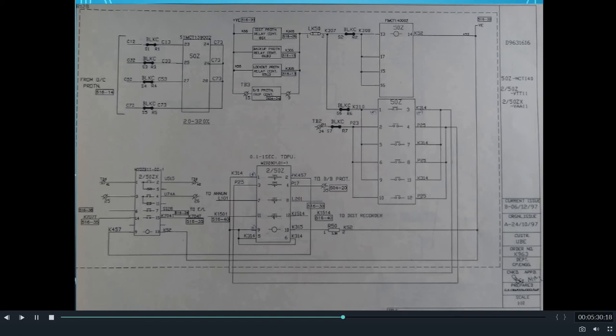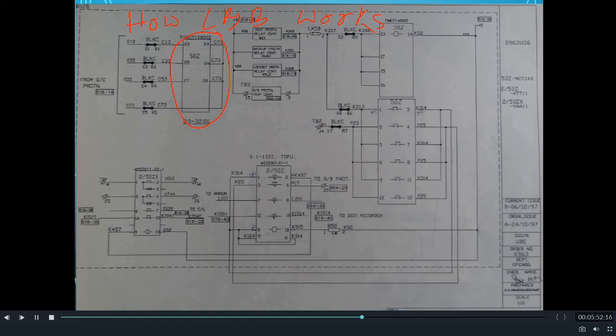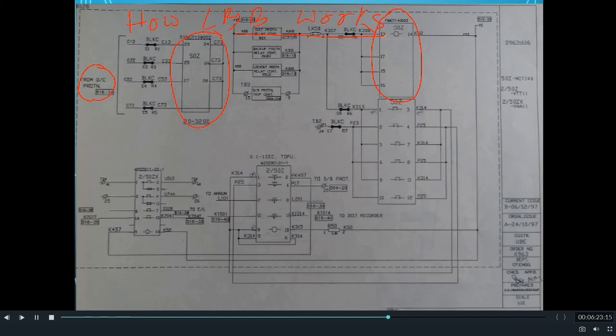Now we will see how LBB signals are generated from the LBB relays. This is a schematic diagram of an LBB relay connected in a one and a half breaker scheme. Looking at the diagram from the top left, we can see the 50Z component — that is the LBB relay — shown for the current connection of the LBB unit. The currents are connected in series with the overcurrent protection relays. Hence, for operation of the LBB relay, there must be current flowing through the LBB relay and through the overcurrent relays — this is considered the first criteria for operation of LBB. Looking at the top right side of the drawing, we can see how the 50Z unit — the LBB relay — is connected for its DC connection. The DC connection to this relay is given through the main protection relay, the backup protection relay, the lockout relay, or the busbar protection relay. This is considered the second criteria for operation of LBB.